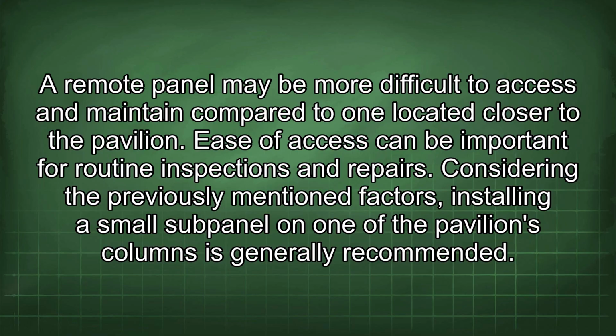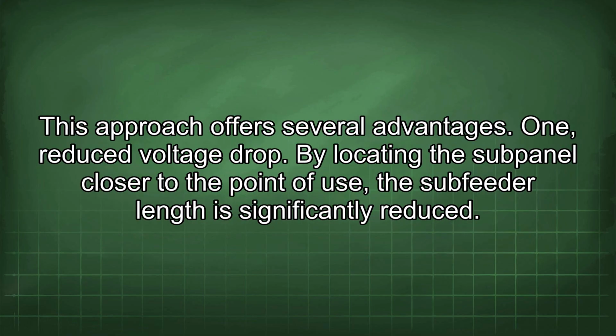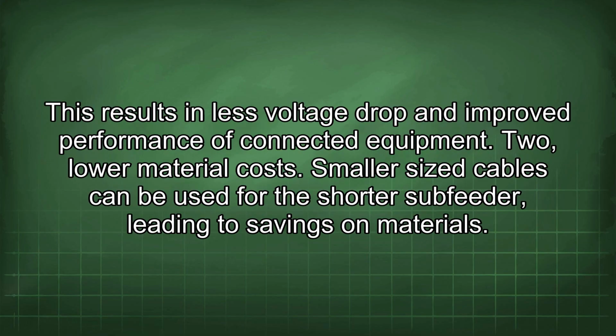Considering the previously mentioned factors, installing a small subpanel on one of the pavilion's columns is generally recommended. This approach offers several advantages. 1. Reduced voltage drop. By locating the subpanel closer to the point of use, the subfeeder length is significantly reduced. This results in less voltage drop and improved performance of connected equipment. 2. Lower material costs. Smaller sized cables can be used for the shorter subfeeder, leading to savings on materials.